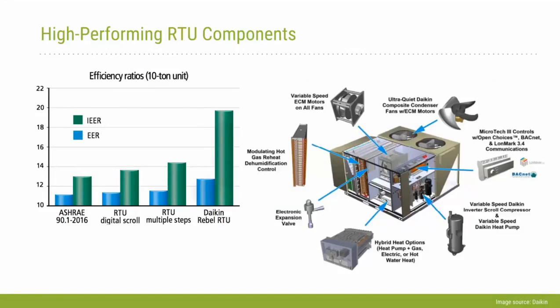The unit that you're seeing here is the one that was tested. This unit actually uses electronically commutated motors for fans. And then it also has a variable speed drive on the compressor motor. These high performance units, especially the ones that are 7.5 ton or larger, may have multiple compressors. For example, a 7.5 ton unit might have a 3 ton and a 4.5 ton capacity, which allows these units to have 3 distinct capacities: 3 ton when only the first compressor is running, 4.5 ton when the second compressor is running, and then 7.5 ton when all of them are running, right?